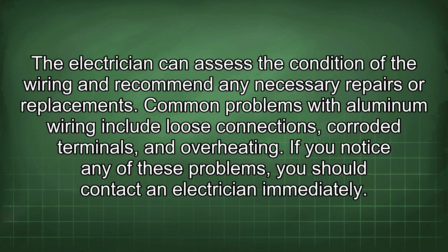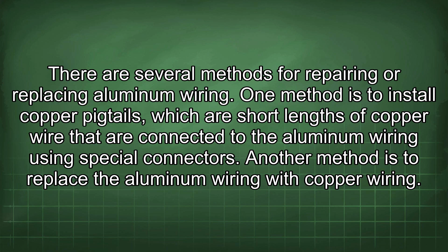There are several methods for repairing or replacing aluminum wiring. One method is to install copper pigtails, which are short lengths of copper wire connected to the aluminum wiring using special connectors. Another method is to replace the aluminum wiring with copper wiring.